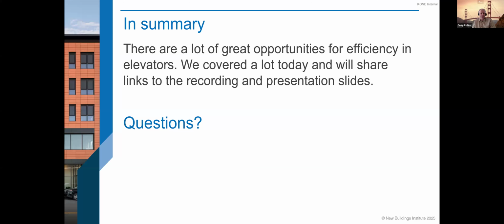Do fire extraction fan and pump systems require UPS systems as well? Yes. If you deploy a UPS for your elevator power and need code-required emergency backup for that elevator power, you'll also need smoke handling fans in your elevator shaft, which are also code-required emergency power, so the UPS system could supply those too. However, the elevator power itself may be classified differently than the smoke handling aspects of the emergency system, so you may need a transfer switch, or multiple transfer switches, downstream of your UPS to differentiate and satisfy your code and AHJ.